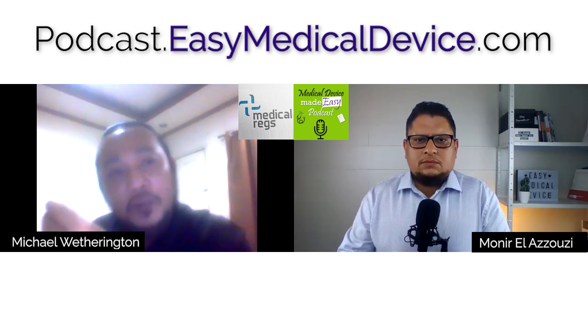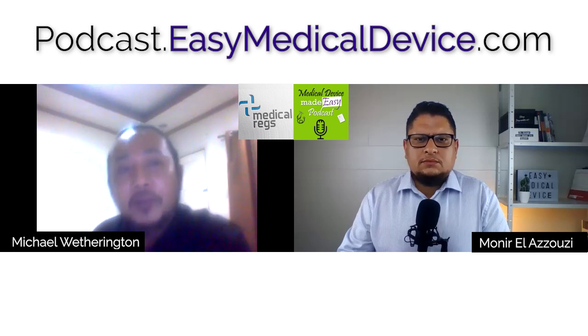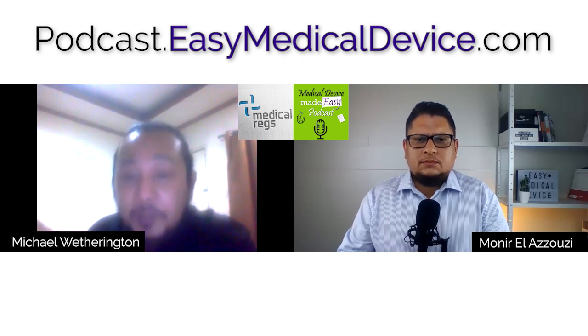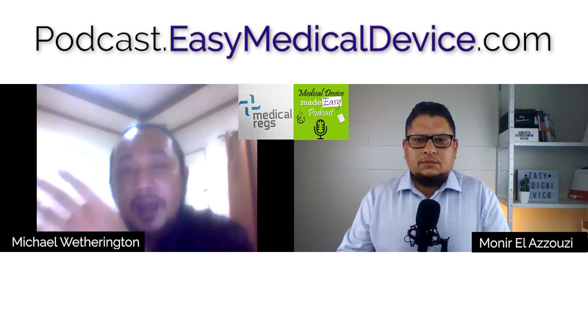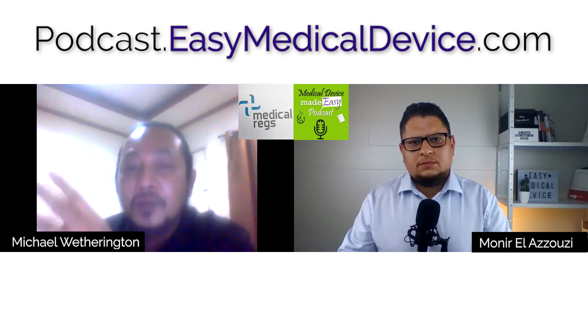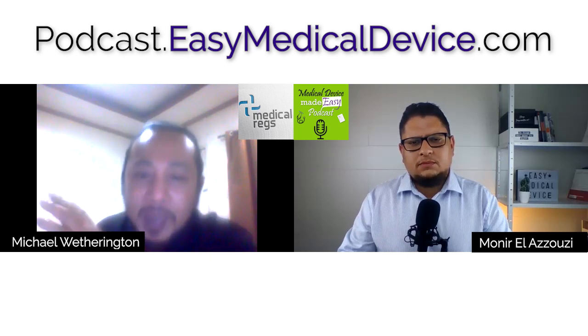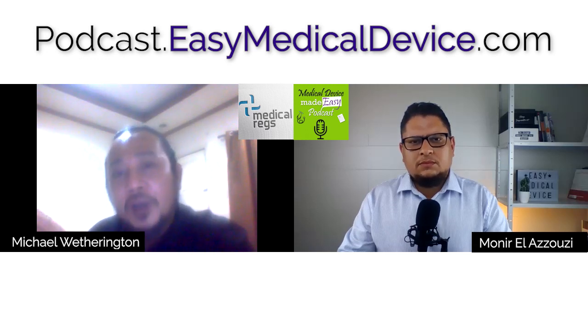Some examples: most active, electrically powered medical equipment will have to be tested for a high-pot test and leakage currents. Those are your key basic tests coming out of the 60601 series. And then you can get into electromagnetic compatibility when you're talking about the collateral standards. So you would pretty much have to do what the testing lab does, at least checking it constructionally. It's a two-stage process for the test lab. They'll check the construction to see if you have the right components, you connected your wires correctly, you mounted your different components correctly, using the right insulation. And then you get into the testing side of the standard: okay, this doesn't apply because I don't have this, this applies because I have this. So it goes through that.